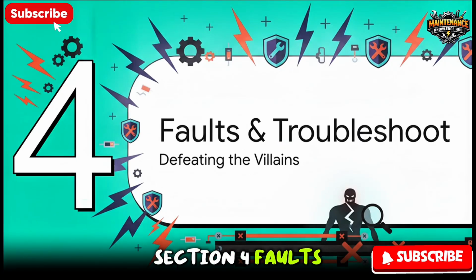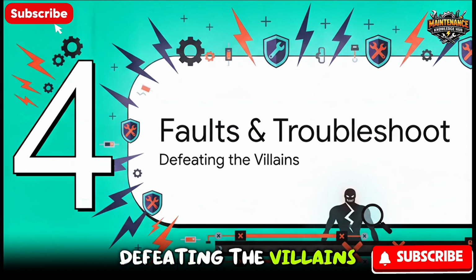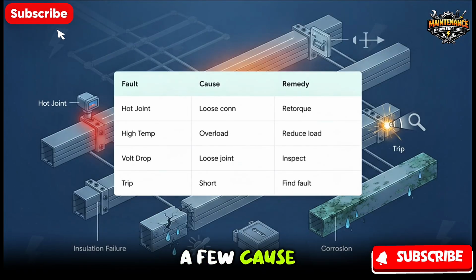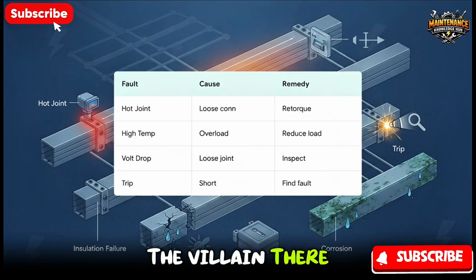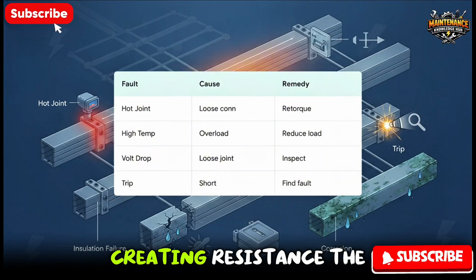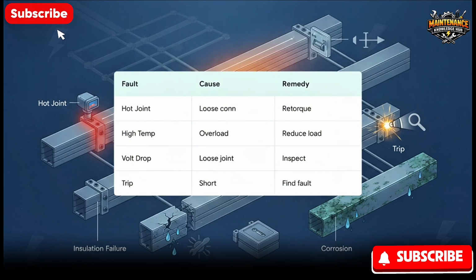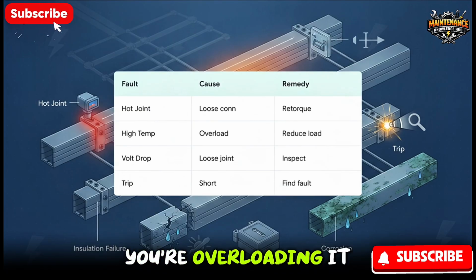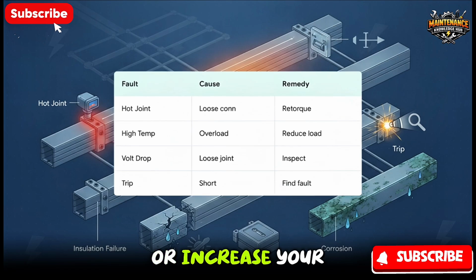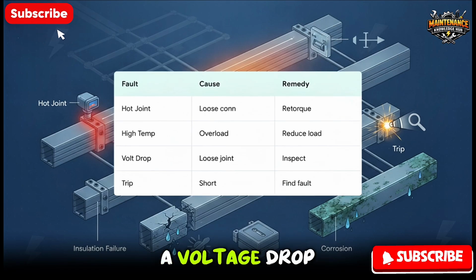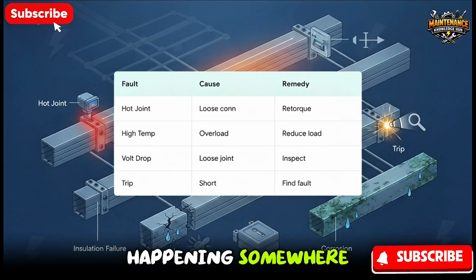Section 4, Faults and Troubleshooting, Defeating the Villains. Let's look at a few cause and effect scenarios for when things do go wrong. Say you spot a hot joint during a thermal scan. The villain there is almost always a loose connection, creating resistance. The remedy? De-energize the system and retorque or replace that joint. If the overall system has a high temperature reading, you're overloading it. You have to reduce the load or increase your capacity. A voltage drop is basically the system telling you there's a loose joint or an overload happening somewhere.